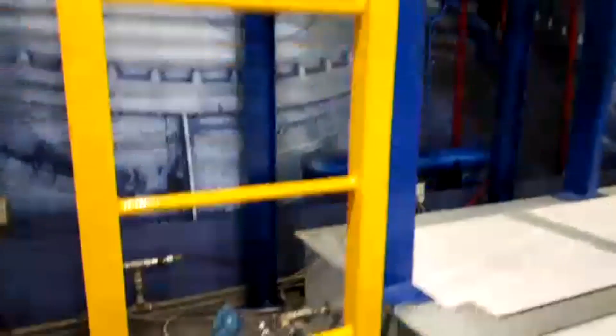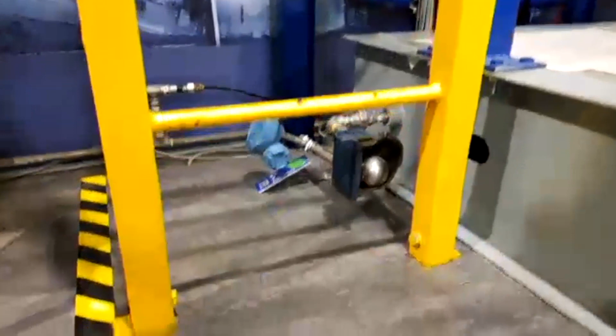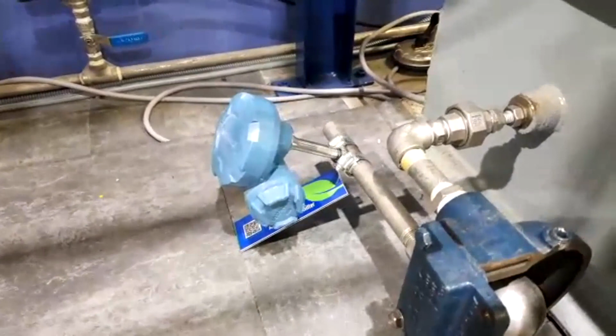Down here by the floor, you can see a steam trap, and also a sensor on it. This is a wireless HART acoustic sensor, really a two-in-one sensor for both acoustic noise and temperature. These values are sent to the steam trap analytics I showed you, which determines the health of the steam trap. Typically you'd inspect once a year, but now you get an update once a minute, so you get immediate notification.